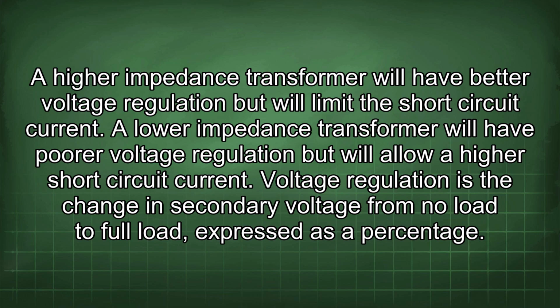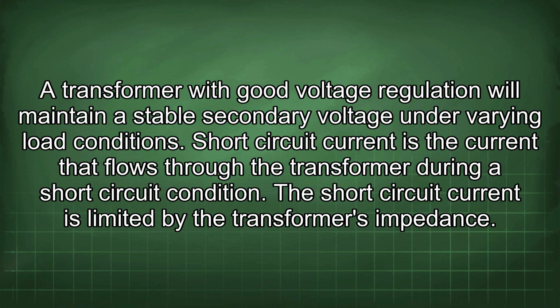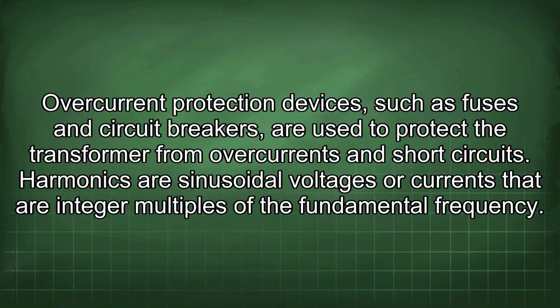Voltage regulation is the change in secondary voltage from no load to full load, expressed as a percentage. A transformer with good voltage regulation will maintain a stable secondary voltage under varying load conditions. Short-circuit current is the current that flows through the transformer during a short-circuit condition. The short-circuit current is limited by the transformer's impedance. Overcurrent protection devices, such as fuses and circuit breakers, are used to protect the transformer from overcurrents and short circuits.